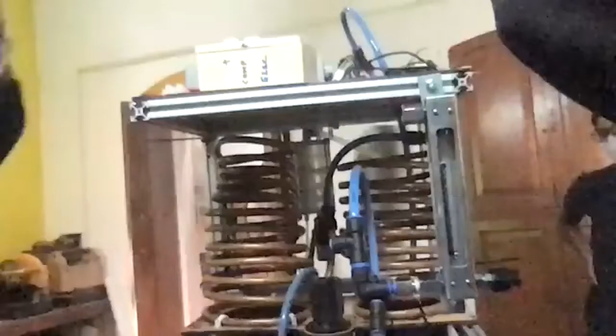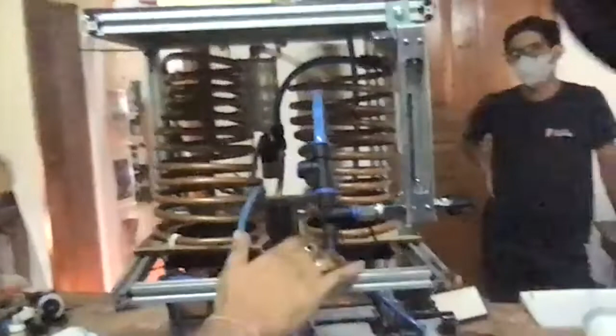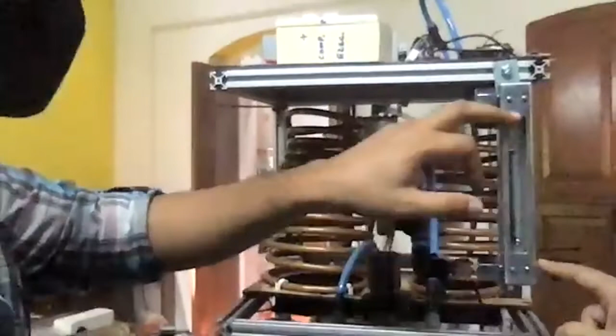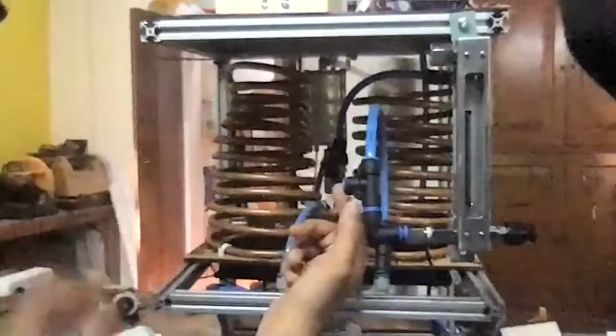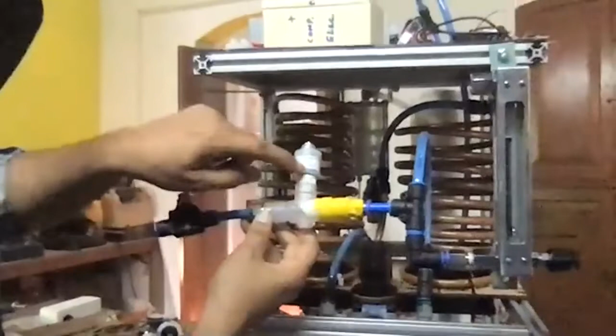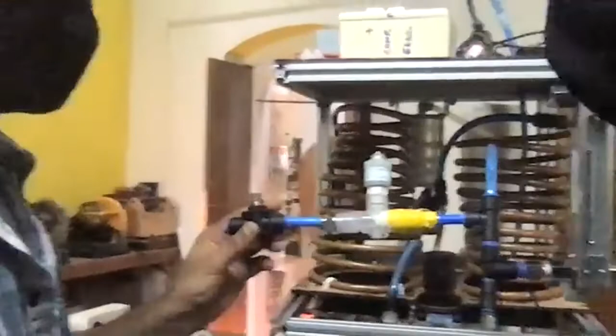How do I explain this? Here's a setup. This is a low pressure regulator. That goes to a flow meter, and that's the output oxygen. But here we have a T, and on that T we have a sensor connected, and the output is a small bleed valve. So we have a small amount of oxygen coming out of here. This bleed valve is almost closed, just like you can't even feel it, just about that much oxygen coming out. So most of it goes out here, and a very small amount goes out through here.